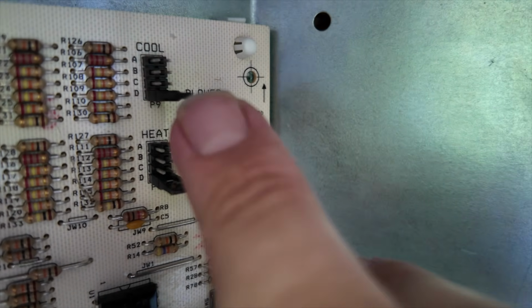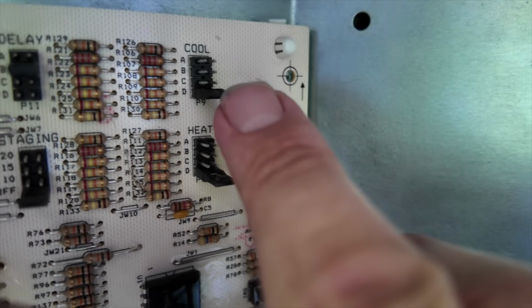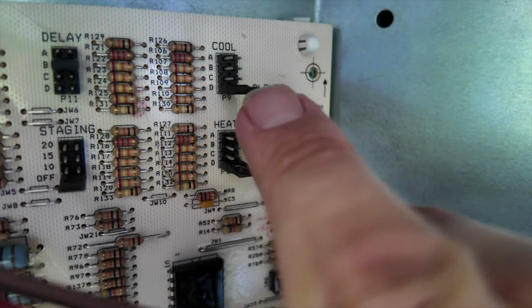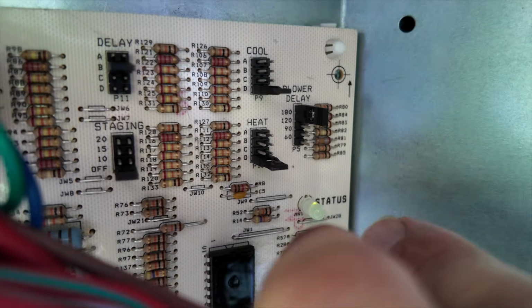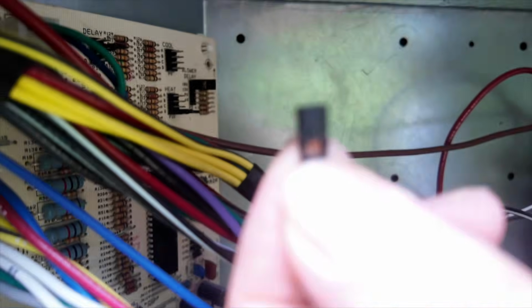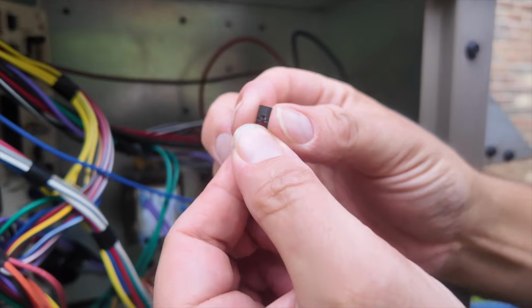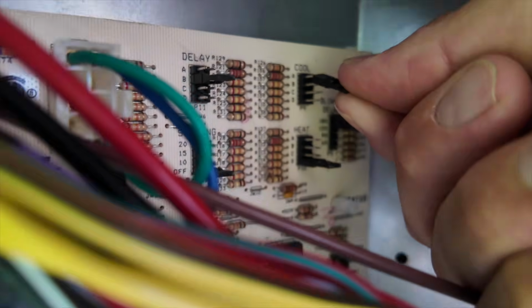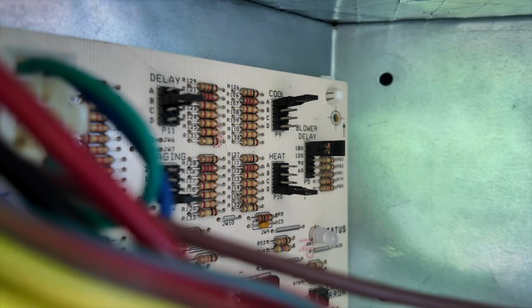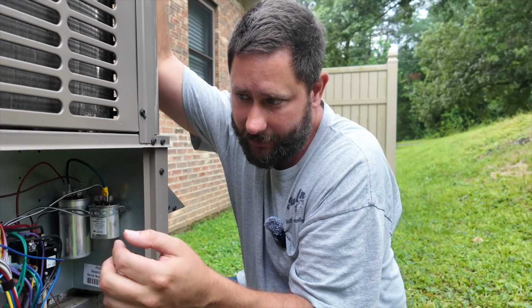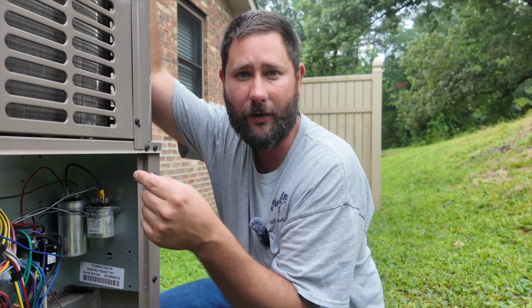Well, if you look at the airflow performance charts in the installation manual, you'll see D is the lowest airflow setting. So I'm going to take that off like this, hold it in my hand, see that? These are for configuring the blower delay or the airflow. I'm going to put that on A. Now we may have to reset power, may not, but now we've adjusted the airflow.